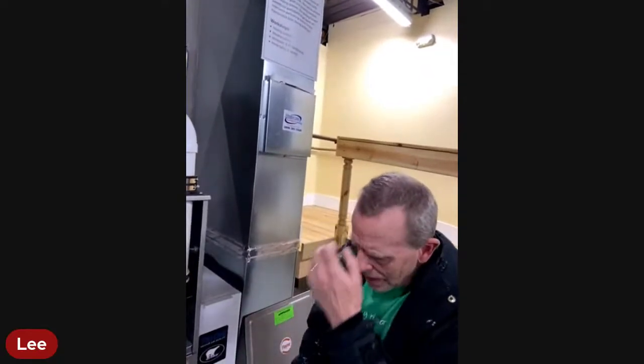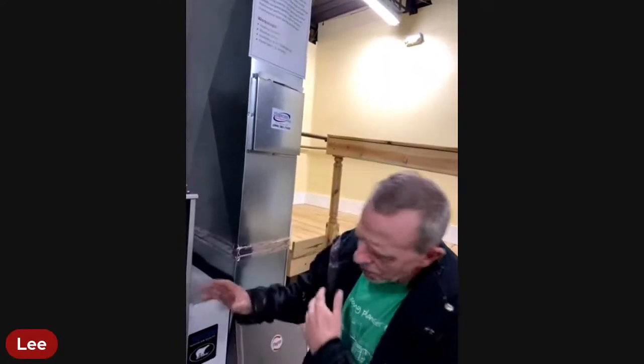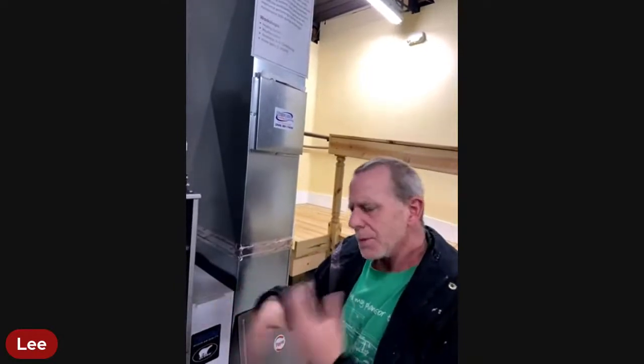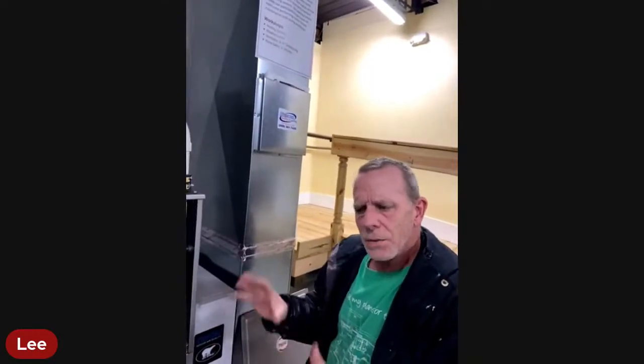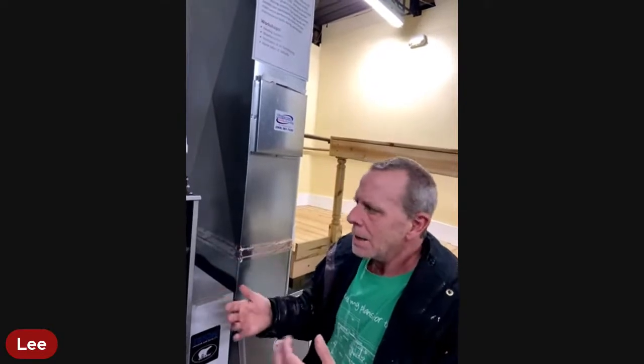What happens is the furnace will try, usually about 3 times, going through its startup cycle. If something goes wrong, it shuts everything down, waits for a second, and tries again. It shuts things down, waits, tries again, shuts things down, and then usually stops, because it doesn't want to wear itself out by constantly trying.